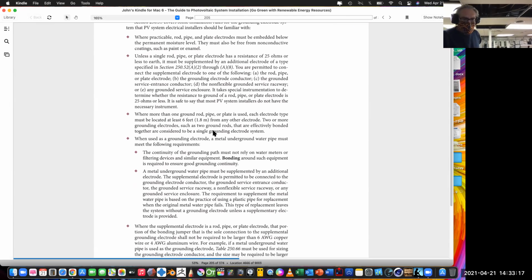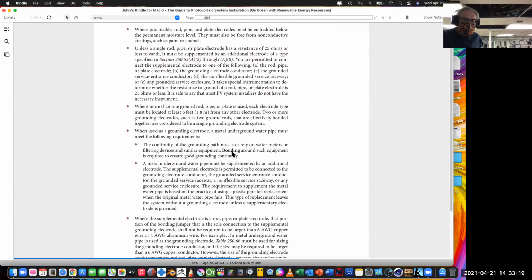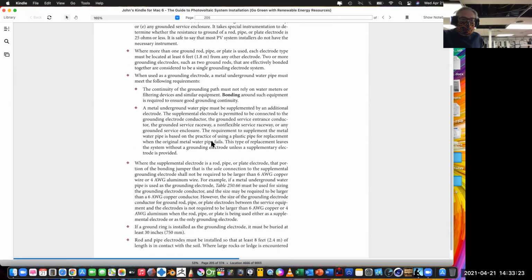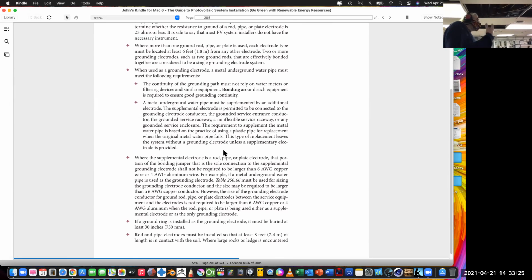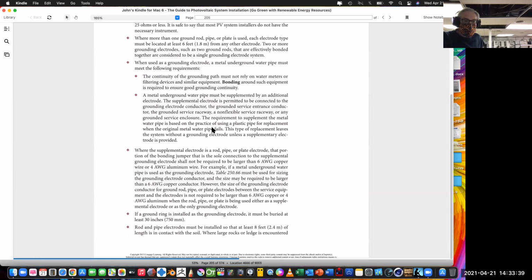Point made. So everything needs to be bonded together. Bonded means all these things need to stay connected. So if we pull that pipe out of the ground because we're removing the well and we don't put a new ground electrode in, we're no longer bonded. So we need to make sure everything that is metal, that is part of the system, is connected to a green wire, one way or another. And we have several cases of that throughout the system. Okay.